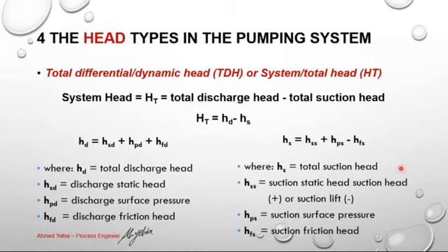The total suction head is the suction static head, plus or minus: plus if the level of the suction is above the pump center line, and minus if the level of the suction is below the center line of the pump.